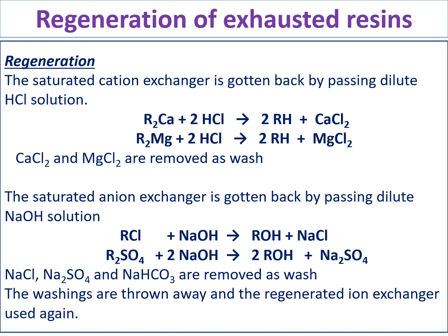When the cation and anion exchange resins are exhausted, they are unable to continue the softening process and need to be regenerated. To regenerate the cation exchange resin, HCl is passed over it, which restores the H⁺ ions. For the anion exchange resin, NaOH (sodium hydroxide) is passed over it, which restores the OH⁻ ions and regenerates ROH. The waste water containing salts from regeneration is drained outside.